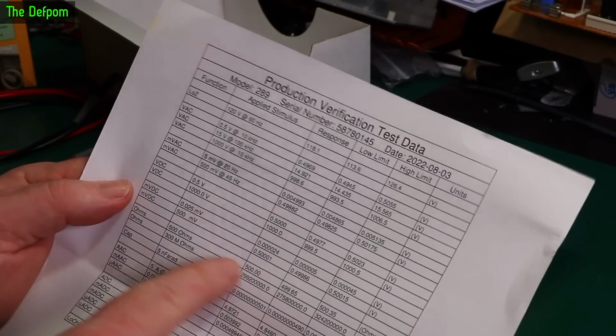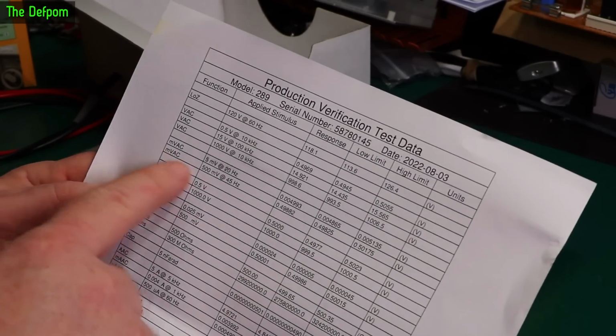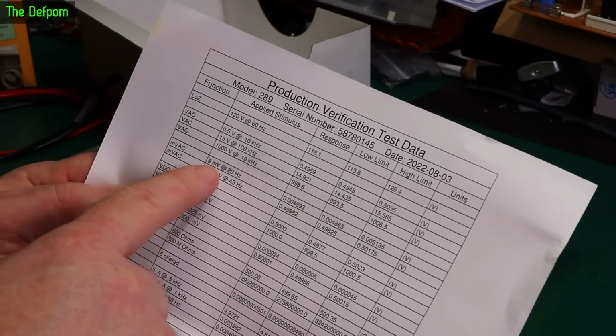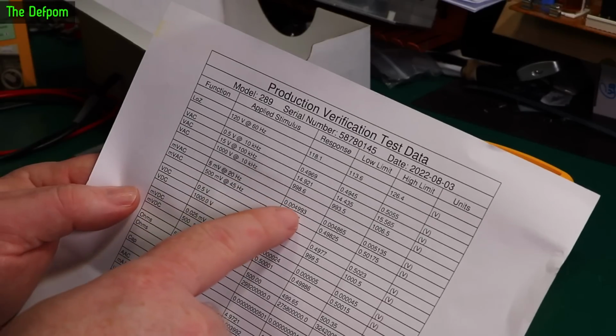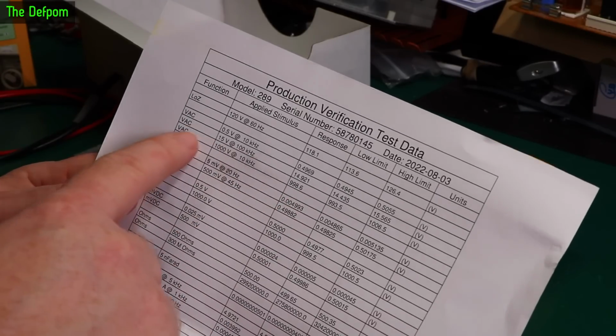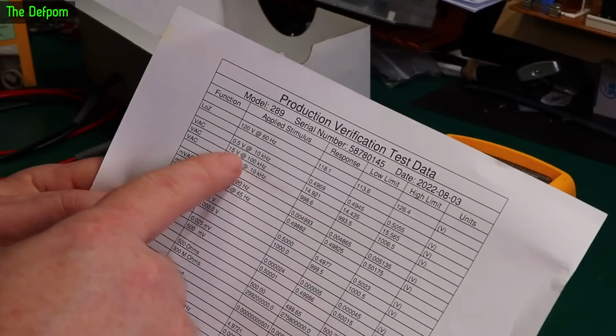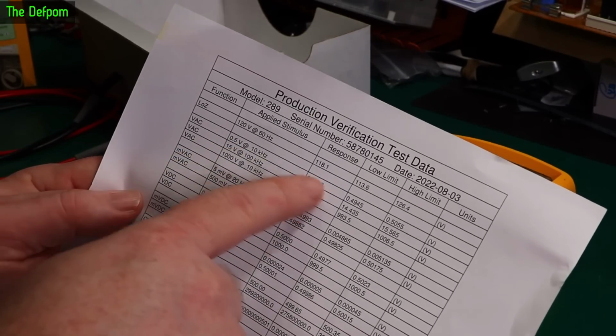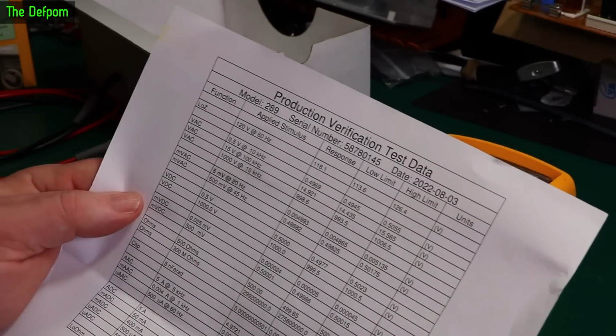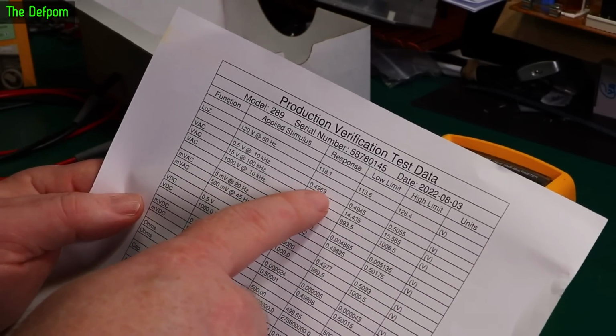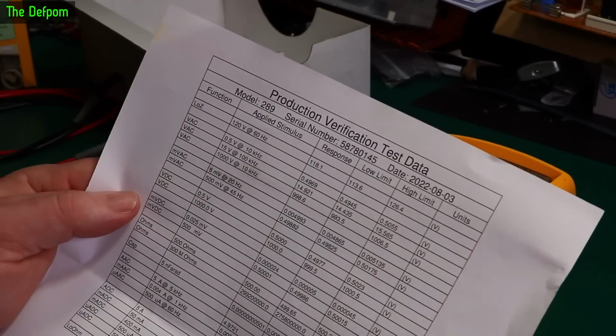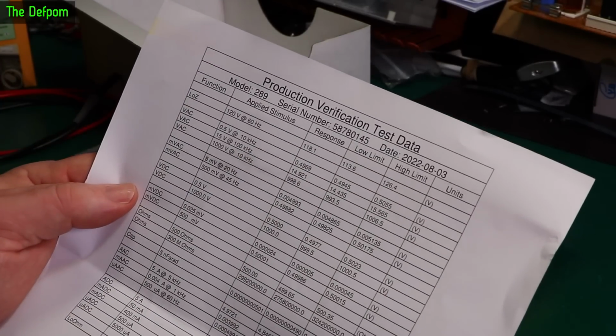DC ranges are pretty good. The millivolt AC one's an interesting one. It's showing 5 millivolts there, but we couldn't see that on the volts AC range. So the lowest that it goes on here is 500 millivolts on the volts range. And then you can see it's reading down by 3 millivolts. That matches what we found.